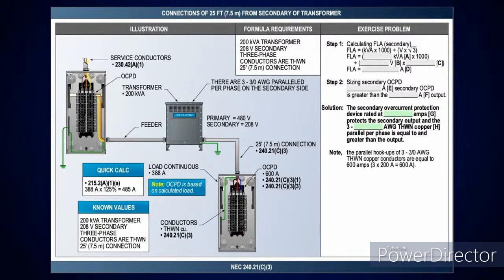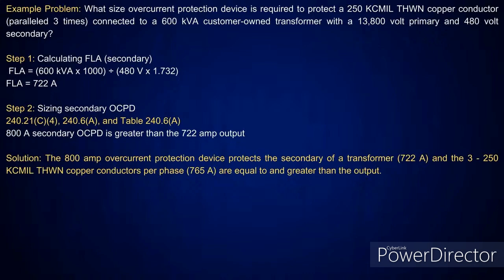All right, now if you notice, this is once again a 25-foot tap. I'm doing the same calculation when I get to transformer secondary conductors, is what I'm trying to point out. When I look at C4, I'm doing exactly the same thing here. I've just got higher voltages. This is a 600 kVA customer owned transformer, and I have a 480 volt secondary. You multiply that times 1.732, that'll give you 831 volts. You divide it in there, it gives you 722 amp output. Well, per 240.4(B), 800 amps or less, what's the next size above that? 800 amps. See that? That's simple.